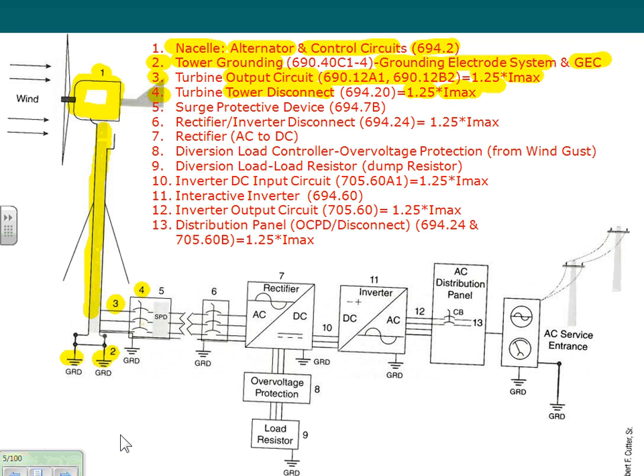Believe it or not, if you read through the whole disconnect section, you can put the disconnect right on the tower, or on the building, or anywhere you want. I think in Georgia we have to do it close enough, visually and accessible to the electrician or the service person. It has to be closer to the house, right to the tower or to the house. And you can put multiple towers on one. Okay, so that's your tower.